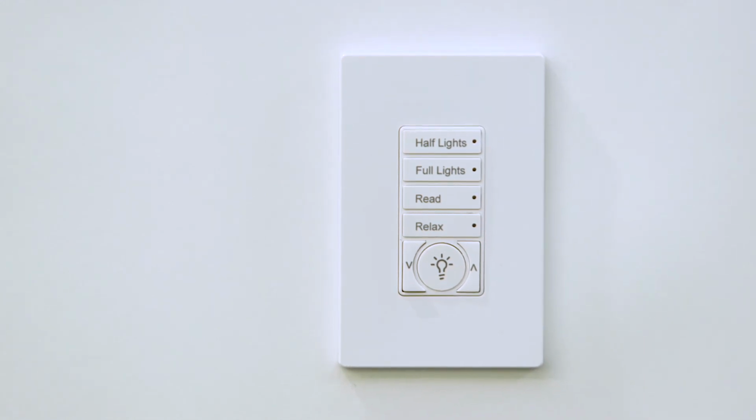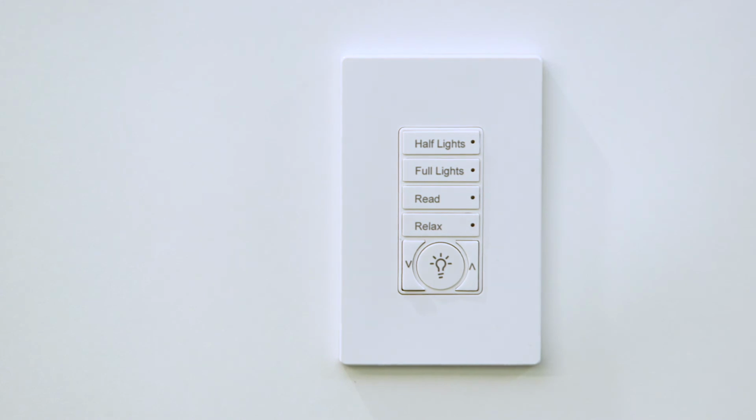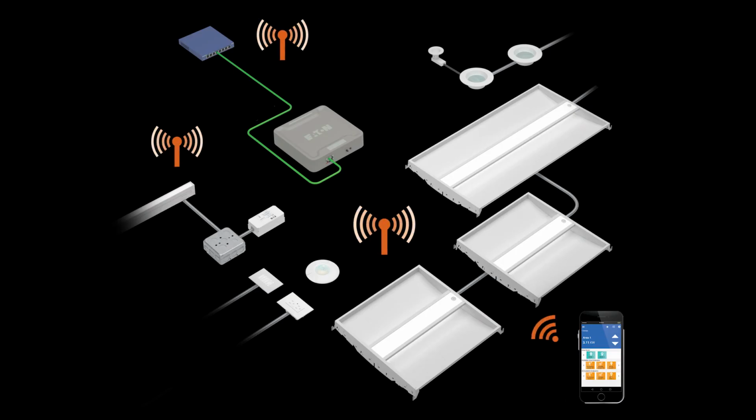At each wall station, press any wall station button that has an LED indicator. The LED on that button will flash slowly for approximately 10 seconds and then stop. The verification of WaveLinx device installation is complete. The WaveLinx system is now ready for the construction grouping process discussed in the next video.